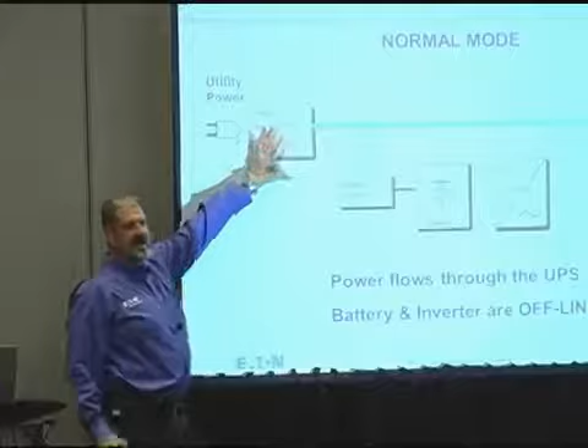If I look at an offline UPS, basically my power components, the battery and the inverter, are sitting offline waiting to be switched into service. My loads are fed directly off of the utility. Sure, I have a surge suppressor, right? It's more designed to protect the UPS than the given loads, but it's there, and the clamping voltage is designed around high voltage spikes, not low transients. But this is the typical power path of this UPS.